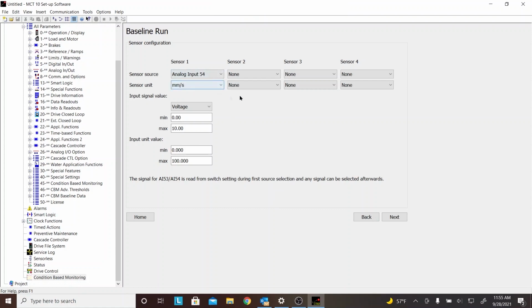Then it says, hey, remember, the 4 sensors are the only thing that you have external that you need to plug into the drive. They are analog inputs to the drive. So we're going to choose the analog input. Now the standard drive has 2, 53 and 54. All the automation drives do. I happen to have a card in here with 3 extra analog inputs, so I can accommodate all 4 sensors plus a speed pod into this drive if I wanted to. Well, for test and display purposes, I'm just going to use 1 analog, and I'm going to use a voltage input on my end. But normally this would be set up for the sensor.